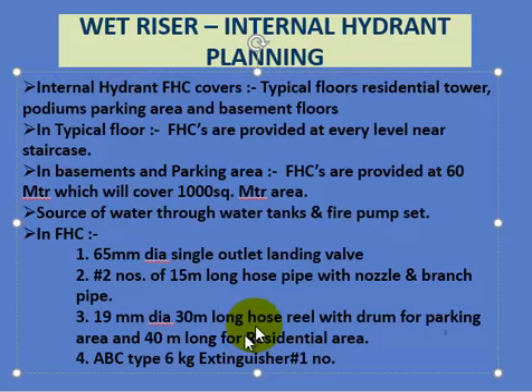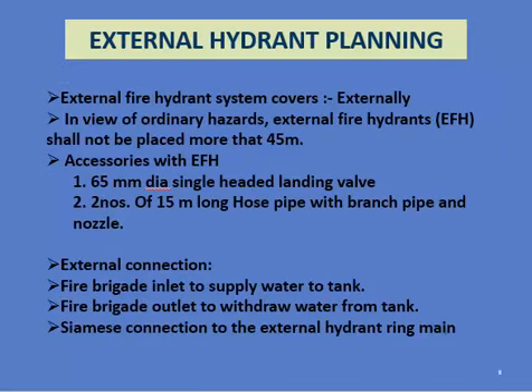ABC-type 6 kg fire extinguishers are also provided. External hydrants cover external areas and are classified as ordinary hazard. External fire hydrants shall not be placed more than 45 meters apart. Accessories include 65mm single-headed landing valves and two 15-meter long hose pipes. External connections to hydrants include fire brigade inlet, fire brigade outlet, and Siamese connections.